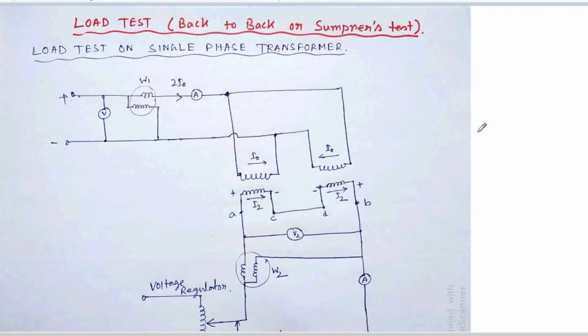Welcome everyone. In this video, our discussion point will be the load test, or back-to-back test, or Sumpner test. This test is done to determine the efficiency of a transformer and the maximum temperature rise of a transformer. But in the case of a small transformer, that means a small power transformer, it can be put on full load by means of a suitable load impedance.